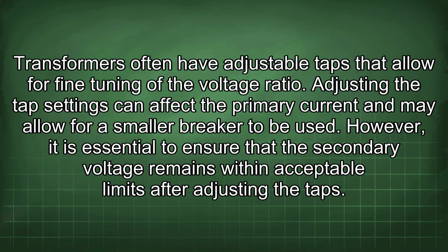Transformers often have adjustable taps that allow for fine-tuning of the voltage ratio. Adjusting the tap settings can affect the primary current and may allow for a smaller breaker to be used. However, it is essential to ensure that the secondary voltage remains within acceptable limits after adjusting the taps.